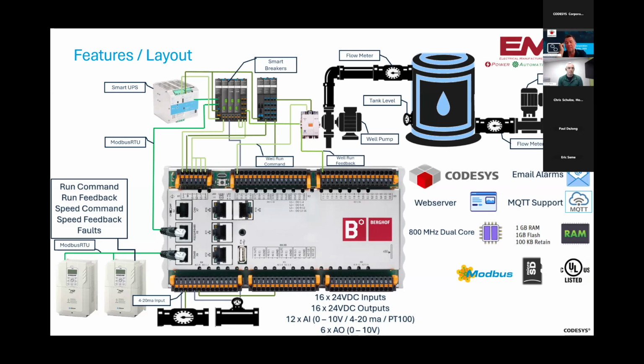Also on the smart breakers, I've got the ability to monitor not only voltage, but current usage for each one of those breakers. So that's a very important feature because when you originally set this up and we go in and configure, we can set a set point to say breaker 2, which is for my analog inputs, it's only pulling half an amp. So next month, if that's pulling an amp, something's changed. And now I can know that's a problem. That's an issue. If I'm getting bad signals from a flow meter, from a pressure transducer, from anything along those lines, I know it could be along that path for current.